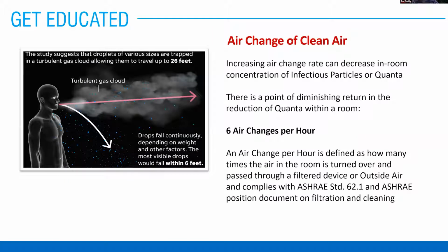The other piece is we are looking at the ASHRAE guidance of air changes per hour of anywhere from 6 to 10 based on your risk. So in a nurse's suite in a school, you might want to move that up to 10. On a typical corridor or classrooms, you can be at 6. But the ultimate guidance is going to be left up to the different designers and practitioners.